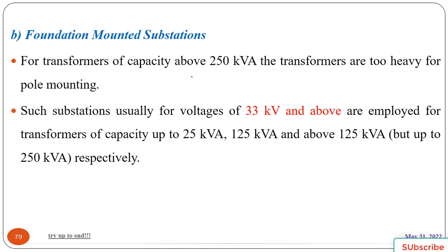Then, the foundation mounted substation. A transformer of capacity above 250 kVA is heavier than one below 250 kVA, and is too heavy for pole mounting. Such substations, usually for a voltage of 33 kV and above, are employed for transformer capacity of 125 kVA and above, but up to 250 kVA respectively.